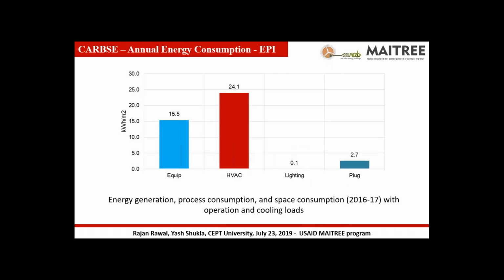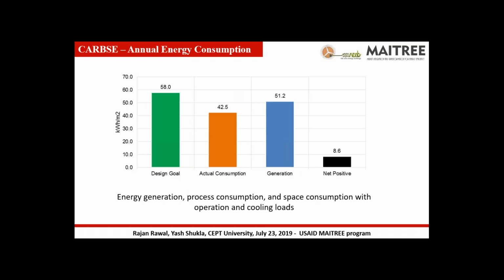In the next slide, I'm going to show the breakup of end use in the building. The equipment, which means the research equipment used in the building, uses about 15.5 kilowatt hour per meter square of energy. The air conditioning system, which uses the maximum in the building, is 24.1 kilowatt hour per meter square. As Rajan Bhai said, the lighting energy use is significantly low, at 0.1 kilowatt hour per meter square, which is commendable and a great tribute to the people who did the daylighting design, because the building is completely daylit. And the plug load, which is computers, laptops, printers and all the other office equipment, uses 2.7 kilowatt hour per meter square.